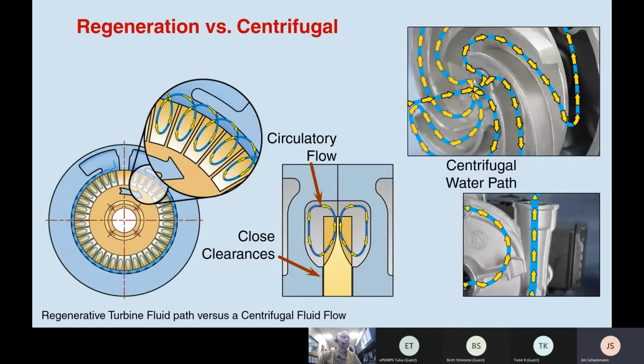Scott, if I may add here, and you're probably going to cover it, if you go back to that impeller that you had, the greater the amount of those quote teeth that are on the impeller, you create more pressure. I don't know if that's accurate. It's actually kind of a mix of impeller versus water channel. A lot of that is engineering that the engineers figure out, because there's some really high pressure pumps that have many vanes, and there's some even higher pressure pumps with bigger diameters that produce more pressure.